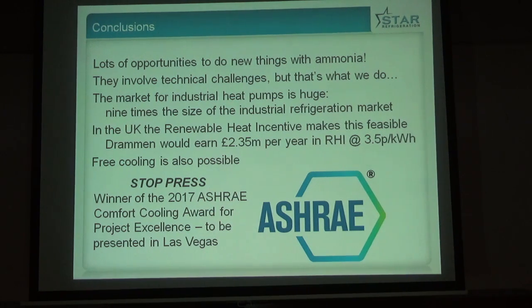If you put one in and you don't maintain it, no matter what the refrigerant is, you will not deliver the financial performance necessary, because it will get fouled up and dirty and less reliable and be offline more often. So the safety issues are a large part of the total equation, but if you look at them on their own, they would lead you to a kind of false degree of comfort.